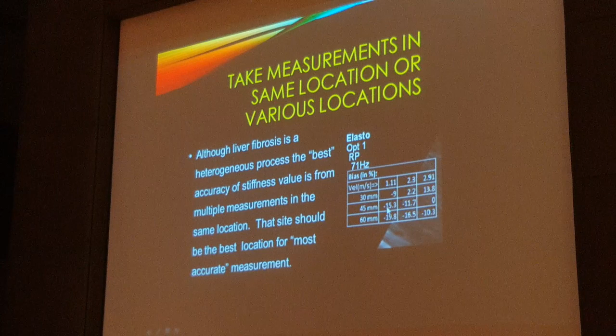And in this vendor, if we had a 2.9 meter per second stiffness liver and we did the measurement at 4.5, they were accurate. But if we did that same 4.5 centimeter in a normal liver, 1.1 meters per second, they underestimated it by 15%. So after this first round, the vendors went back and did corrections into their system and factors to make this better. I think, again, right now, the maximum variability is about 10% within a system. But again, changing the depth is going to give you different measurements. So you want to take all your measurements at the same depth.